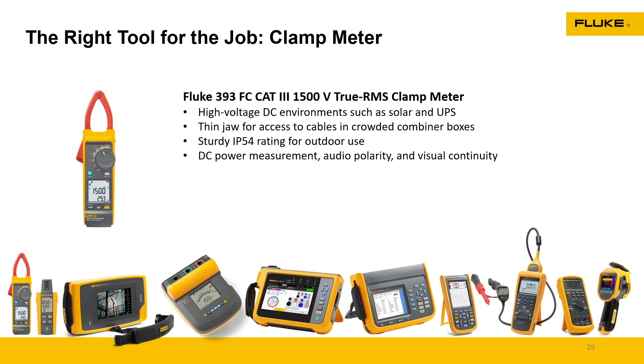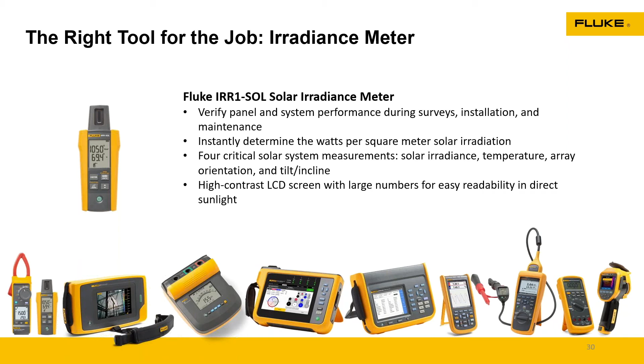Also, as we mentioned, we talked about an irradiance meter. Now, every one of these solar panels has a nameplate on them. Based on that nameplate, at a certain amount of irradiance, you can then determine how much voltage and current is coming out. We've got to know what that irradiance looks like. So having an irradiance meter that gives you that information will help you determine if that panel is outputting correctly. You may not even see anything on the panel itself. There may be no cracks, no shorts, but there's something internally causing that panel not to give out the appropriate voltage and current based on the irradiance. This irradiance meter here will actually measure the tilt, because we want to make sure the tilt is right, and temperature plays a big role in the solar panels themselves. If they get too hot, there's a degradation that happens in the panel itself. So we want to make sure that the temperatures are good, the tilt is great, and the irradiance is working. All of that's crucial to what the solar output of the panel, or the voltage and the current, would look like.